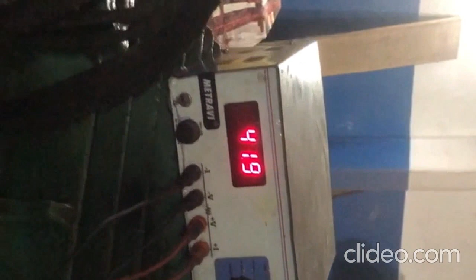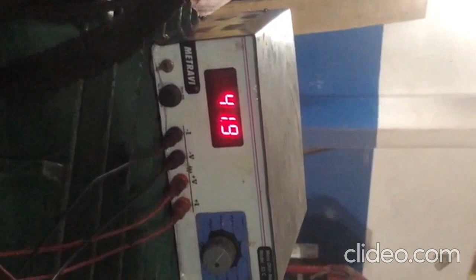Let's take the next one. So the readings are 42, 41.8, and 41.9. The minor variance is because of the contact, which may not always be uniform, and the clippings may not always be uniform. This much of minor variance is acceptable.